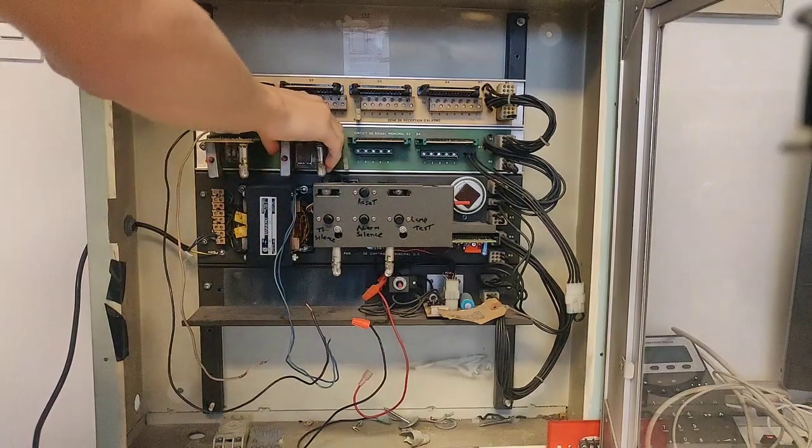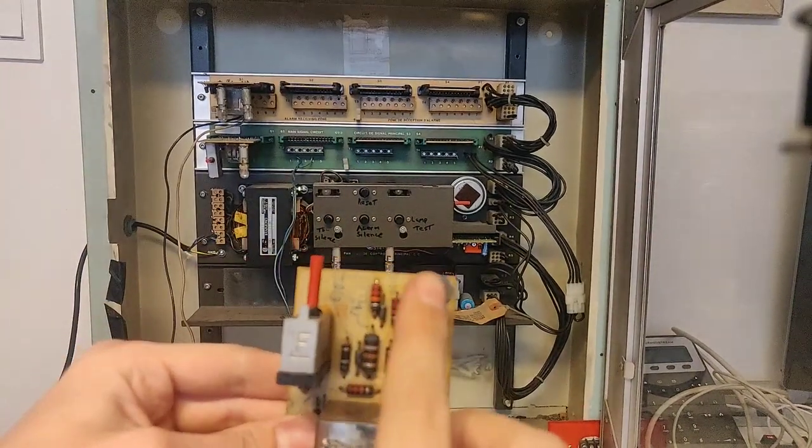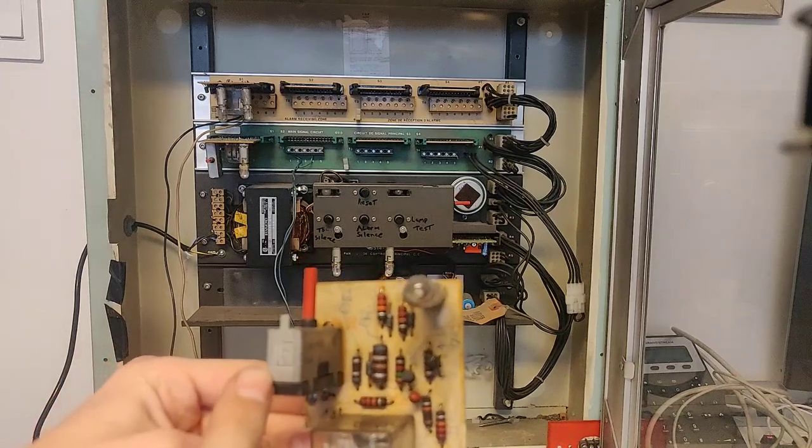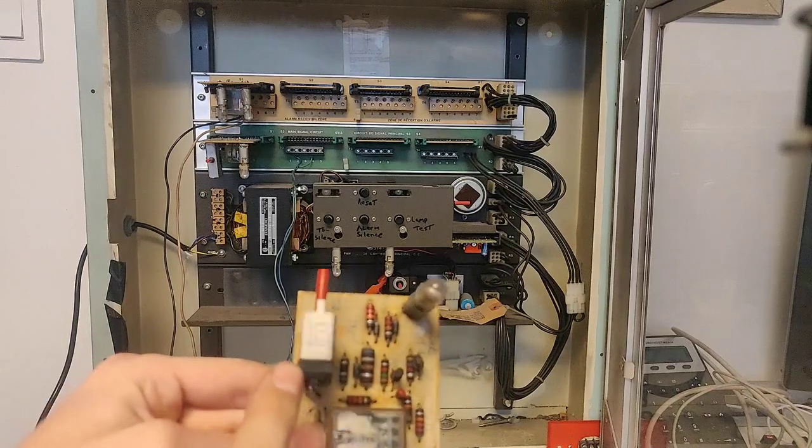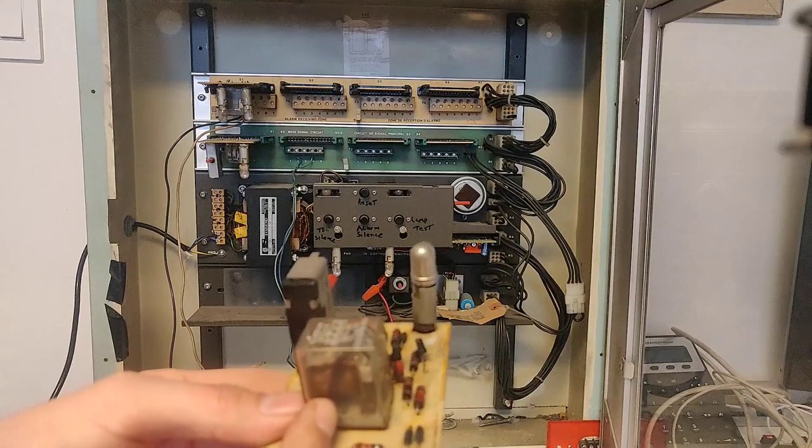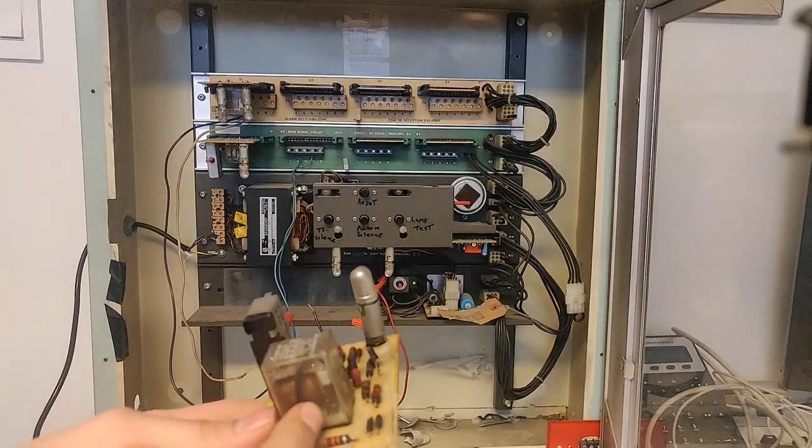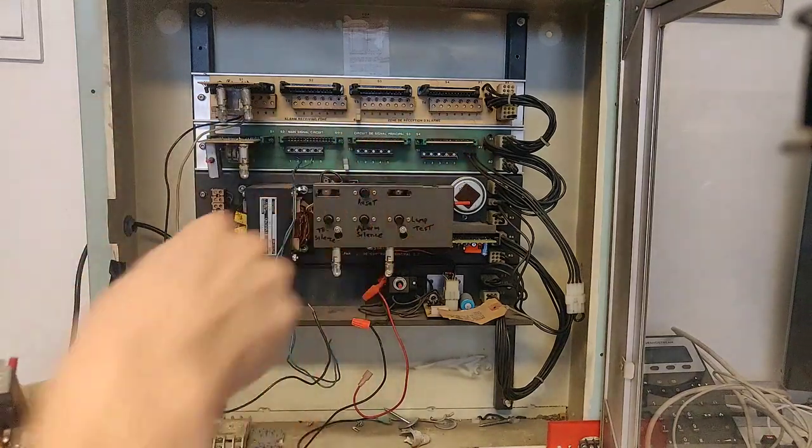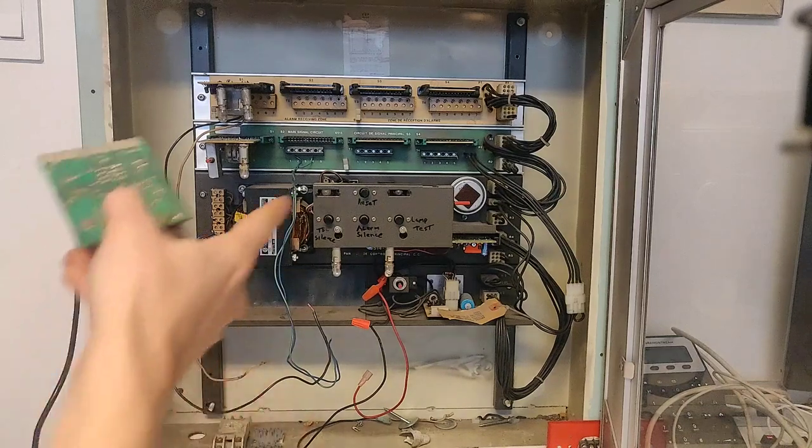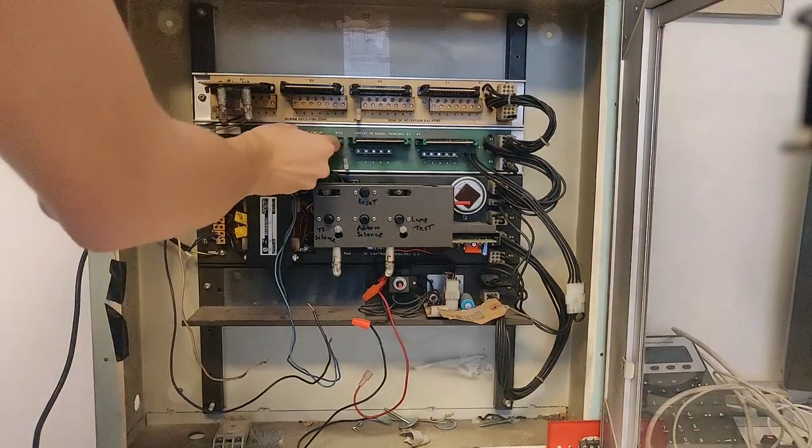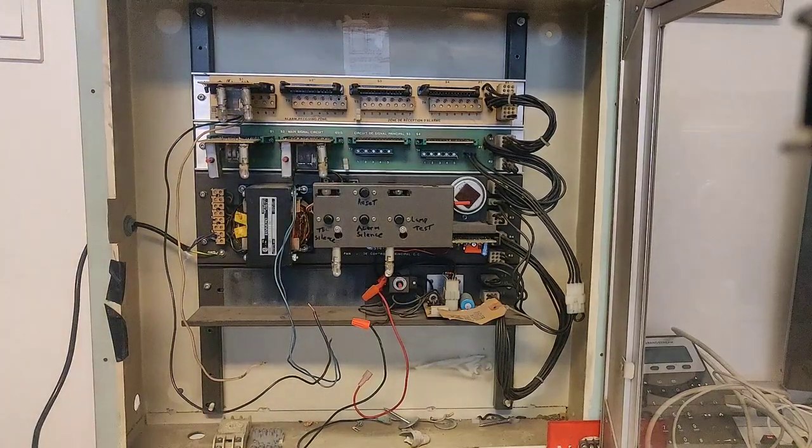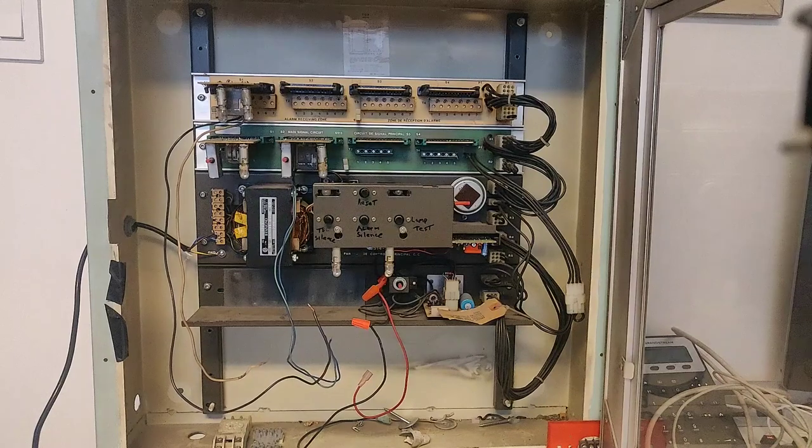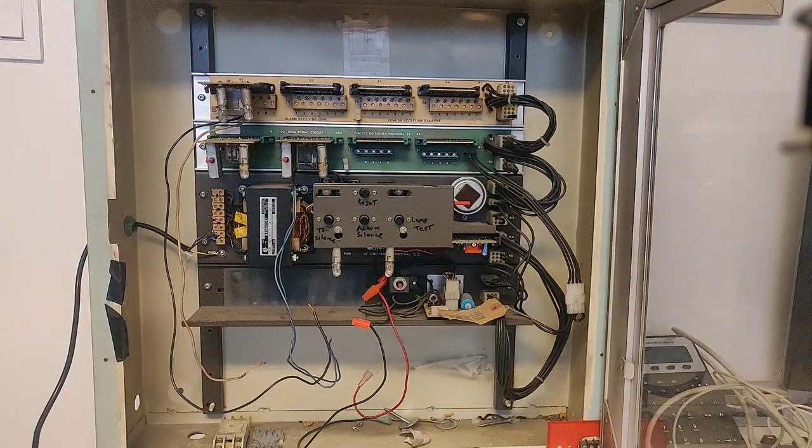Now let's take a look at the alarm card. So it's just got one light which is a trouble. This is for overloads—in case the panel gets too much current draw, this will trip, or it'll just trip if you offend it or look at it the wrong way. That relay clicks on for the alarm circuit. So the contacts, sometimes the contacts will burn, especially if you're working with a coded system. This will click out to do the codes. This particular panel is only capable of a continuous output on the NAC circuit.